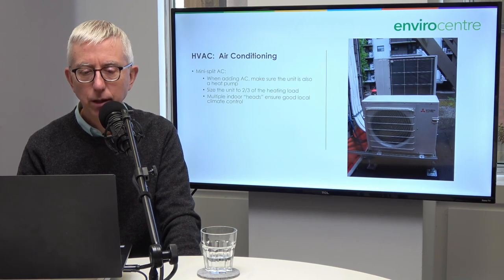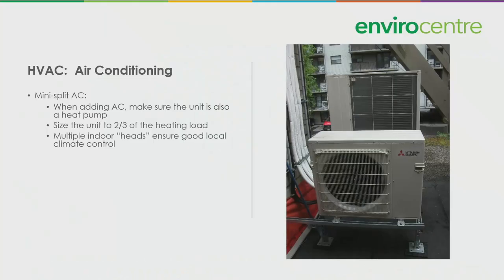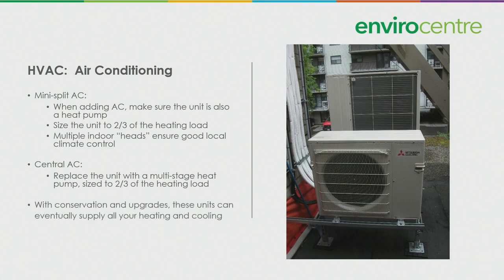Air conditioning. If you have mini split AC, and a lot of restaurants and so on are buying these mini splits, make sure that the unit you're adding is also a heat pump and get it slightly oversized. Size the unit to about 2/3 of your heating load. Multiple indoor heads will ensure good local climate control. If you have central AC, replace the unit with a multi-stage heat pump sized to, again, 2/3 of the heating load. With conservation and upgrades, these units can eventually supply all your heating and cooling.